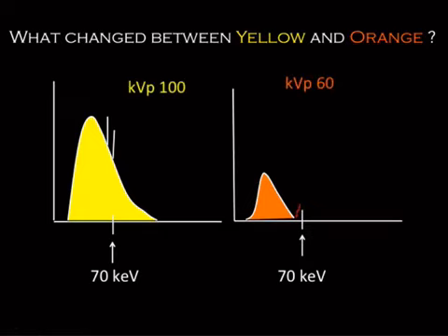So the kVp was changed, and it was lowered to the point that it didn't meet the threshold that it needed to get those characteristic peaks. Remember, that was around 69.5 for tungsten to be able to generate that characteristic X-ray from the K-shell. You had your K-shell threshold. Well, we're below the K-shell threshold, and we could never have more energy coming out than went in, so we didn't put enough in. This guy put enough in. So that's what it looks like when you had insufficient kVp to generate an X-ray.